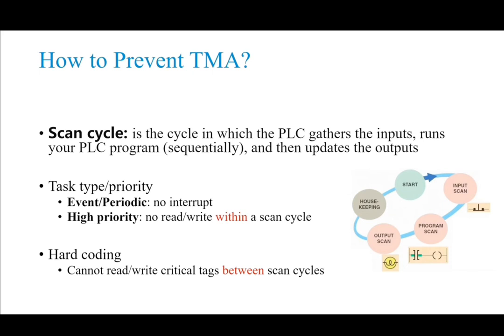Before that, let's first review an important notion of PLCs: the scan cycle. A scan cycle is a cycle in which the PLC gathers inputs, runs the PLC program sequentially, and then updates the outputs. PLCs operate by continually scanning programs, repeating this process many times. The PLC program can run different types of tasks such as continuous, event, or periodic. Event and periodic tasks cannot be interrupted by communication tasks. So in a periodic task, tag write operations cannot be done within a scan cycle.